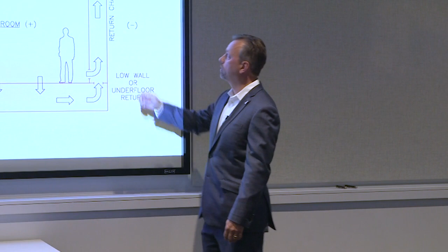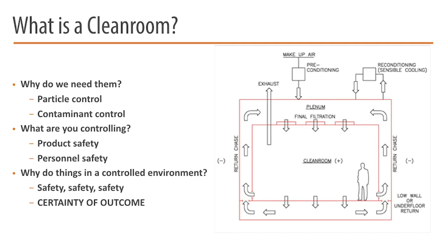Whatever you're pushing into the room, you overcool it to wring out the moisture, then reheat it to get within the tolerances you need before pushing the air into the space. Unfortunately, much of that nicely conditioned air will go out the exhaust stack. Then the other component is sensible cooling. So you've dealt with the environmental conditions, but what about heat gain from people in the room, or heat given off by processes and equipment located in the room? We'd call that sensible cooling, and there are a variety of approaches you could take to providing it. So again, at a high level, that's your clean room.